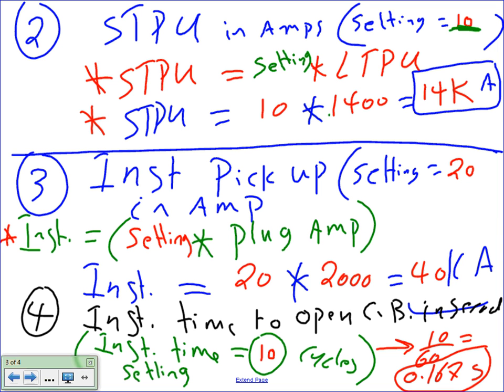Is that typically how it's set as well? How do you set it on the breaker? How is this a typical setting? Right, back to the coordination. Yes and no. I just mean when you turn something on the device, yes, it will be 10, 9, 8. Cycles, right? It will be in cycles. Yes. In cycles. For the most part.